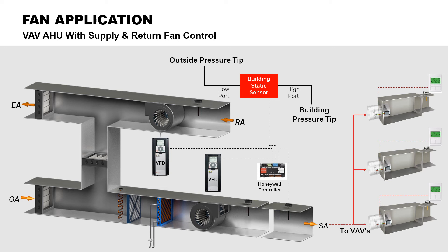For the return fan, the VFD modulates the fan based on building static pressure. Design requirements specify how much outside air is needed based on the number of people in the building and how it's used. The outside air damper modulates to deliver this outside air, and as it does, it affects the building pressure. The building static pressure is kept constant by modulating the return fan with a VFD.